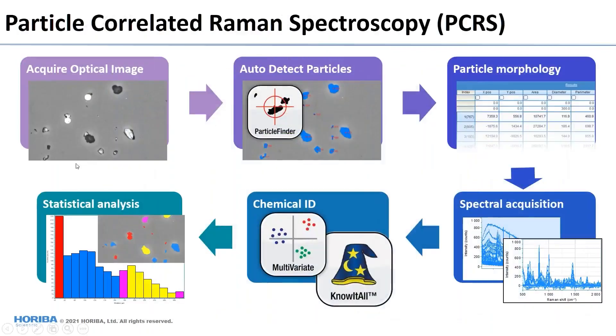How does Particle Finder perform PCRS? It takes an optical image first and detects particles — the particle has different contrast from the background — automatically performing particle morphology analysis including locations, counts, sizes, ellipse ratios, and circularity. It then records Raman spectra from individual particles, with an option to record a map of a particle as well. You can analyze the Raman spectra using multivariate analysis or by searching reference Raman libraries for identification. You then get statistical analysis — size distribution of chemical ingredient A, ellipse ratio distribution of chemical ingredient B, and so on.